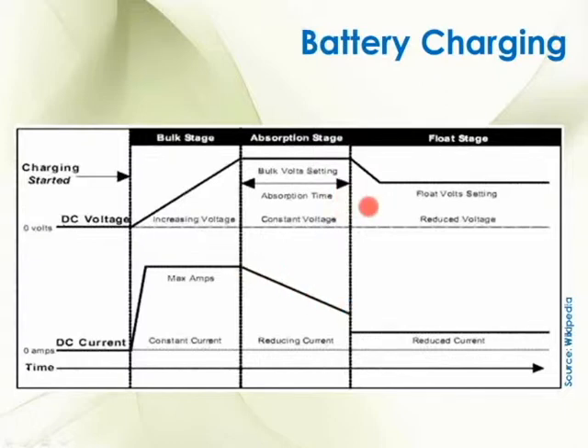When my batteries are totally full and the charging process is pretty much done, my charger is going to go into what's called the float stage. The float stage is really just a trickle charge that keeps the batteries topped off. And as soon as you use some of the power from the batteries, a good charger will realize that and go back into the bulk stage and start the process over again. Some chargers have to be restarted manually, but that's pretty rare these days. Most charging equipment goes into the float stage automatically.